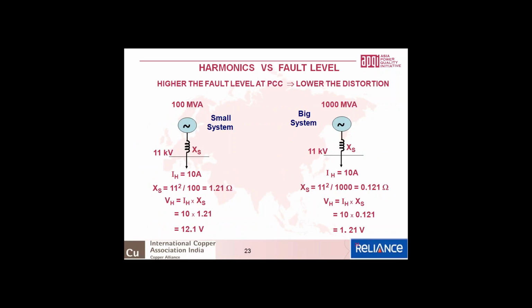On the left-hand side is a 100 MVA small system. On the right-hand side I have shown a system that is 10 times larger, a 1000 MVA big system. Let's assume that a 10 amps harmonic current is injected in both systems. In the small system, the system impedance at 11 kV is voltage squared by 100, about 1.21 ohms, into the harmonic current. Therefore, the harmonic voltage generated is about 12 volts.